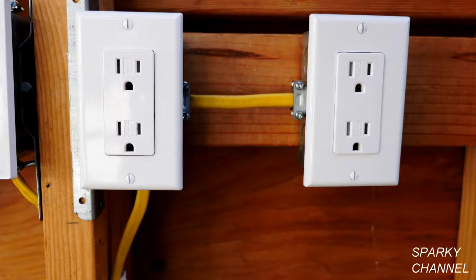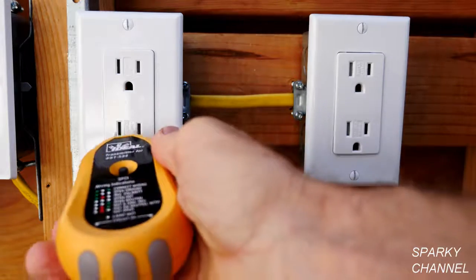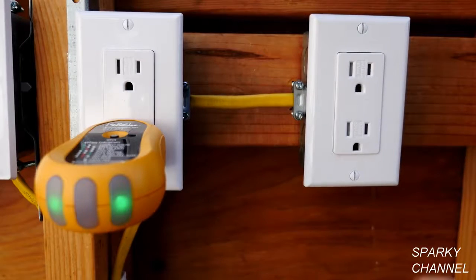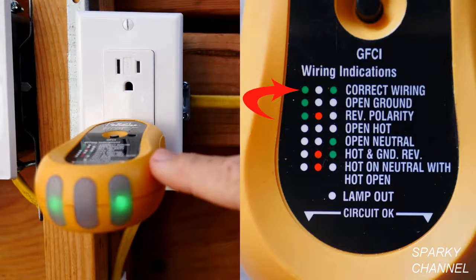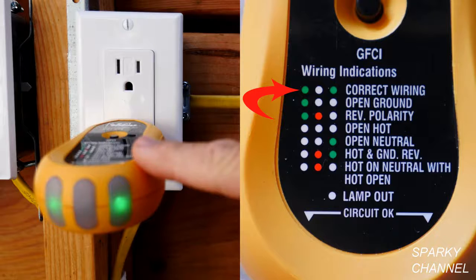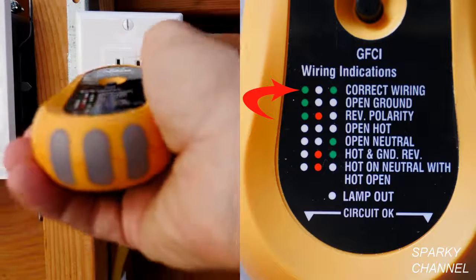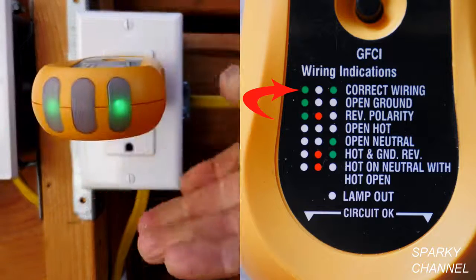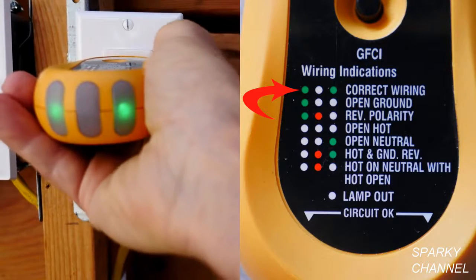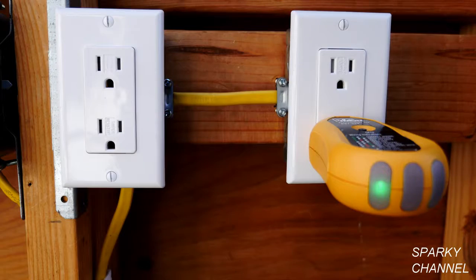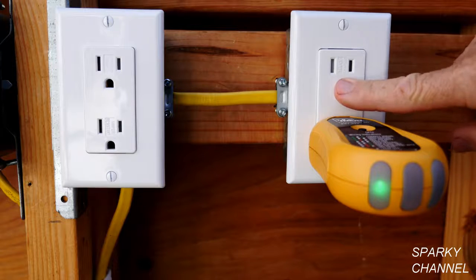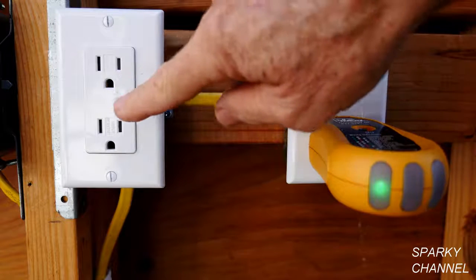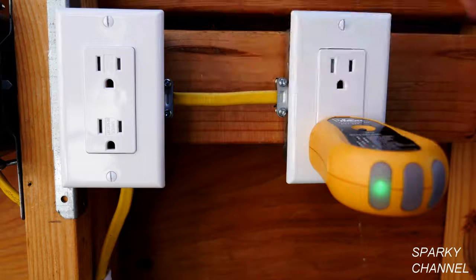Also, test all the outlets on the circuit to see what's happening in the whole circuit. So this is the next outlet on the circuit and we see that this one is, if you look on the index, correctly wired. So this one has a ground. So we found out some important information here using our outlet tester. We found that this receptacle here has an open ground, but that this receptacle right here is wired correctly.